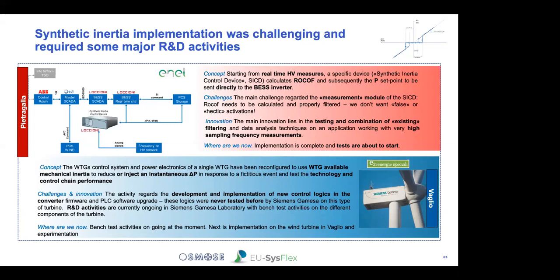So trying to use the kinetic energy stored in the rotating mass, there were some modifications to be done in the converter firmware and in the PLC software. These logics were never tested before by Siemens Gamesa on this type of turbine. So there are tests at the moment going on in the bench test in Vaglio, and the implementation is therefore coming in the following week once these tests are over.